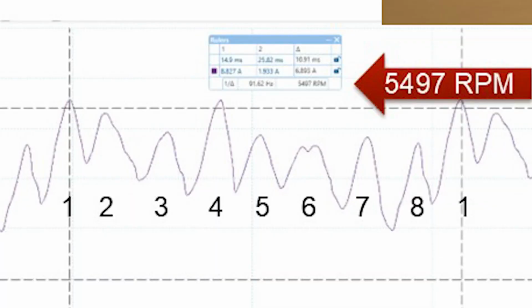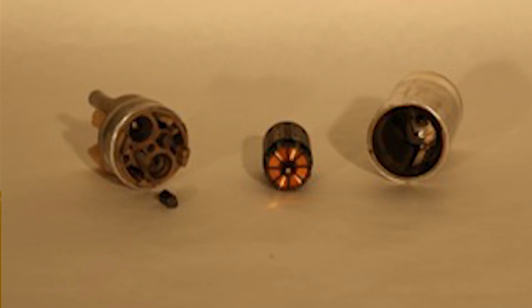The other thing is brush contact. So if I look at this pattern and I see one little irregularity, I put a cursor on it, and another cursor where it reoccurs, that's one full revolution of the fuel pump. I can tell how many commutators I have by doing that. On this one I have 8 commutators. The picture up there shows us 8 slices of pie, or 8 commutators. You can see it's all in copper.